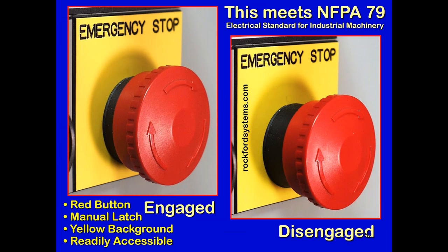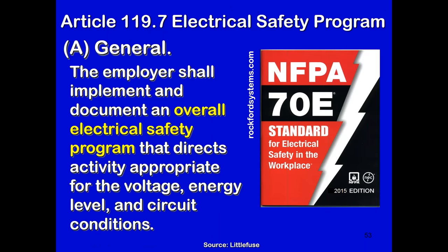NFPA 79 is the electrical standard for industrial machinery that includes things like emergency stop buttons with four basic principles. You got a red mushroom-shaped button, a manual latch, which you see is engaged on the left side but released on the right side. So you have to release it to pop the button back up, go back to your regular controls, and start up the machine. It's got a yellow background, and you have it readily accessible to the operator. Four basic principles for emergency stops that, again, come from the Electrical Standard for Industrial Machinery, NFPA 79.